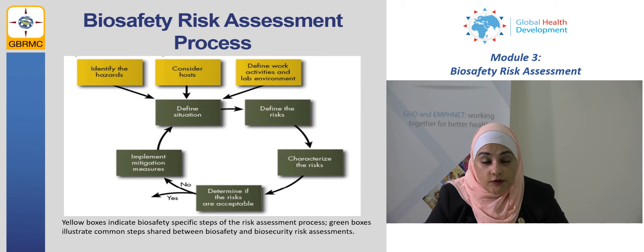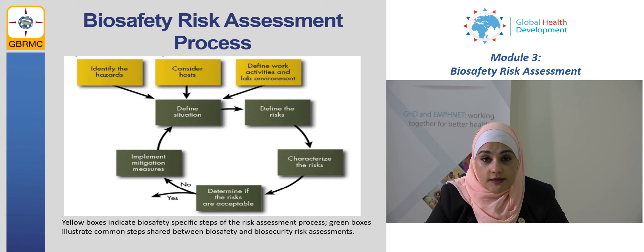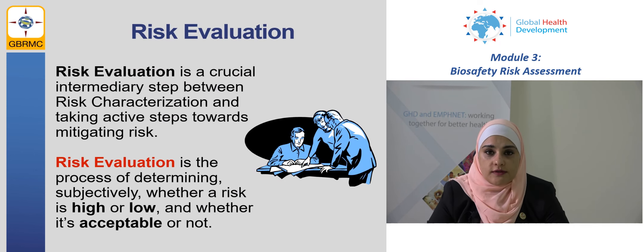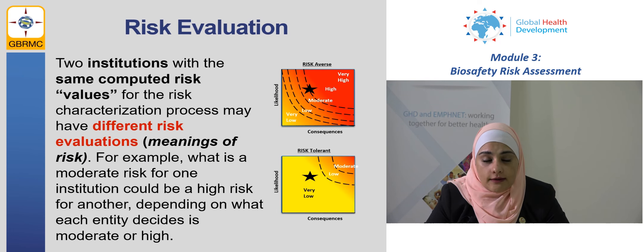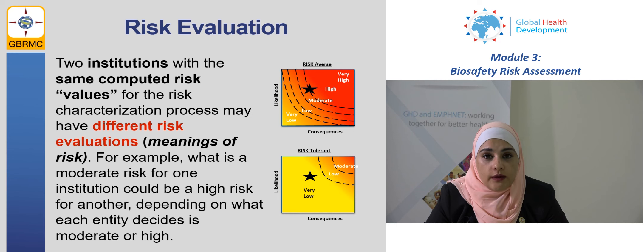To conduct a risk assessment in our laboratories, we need to carry out many of these scenarios, being very specific and collecting factors related to our work and our pathogen to determine the likelihood and consequences and represent them on a graph. For a facility-wide risk assessment, we gather all of this information together into a comprehensive process. The biosafety risk assessment starts with defining the situation by identifying hazards, gathering information about the host and pathogens, and determining the level of risk. After risk characterization, we perform risk evaluation — deciding if the risk is acceptable. If accepted, we proceed; if not, we implement more mitigation measures and reassess.